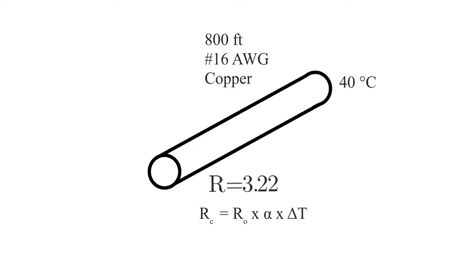So let's say that our room is actually 40 degrees. This calculation here was based off of 20 degrees, so our change in temperature is going to be 20 degrees. Also, when we are dealing with a copper conductor, it has a temperature coefficient of 0.00393.